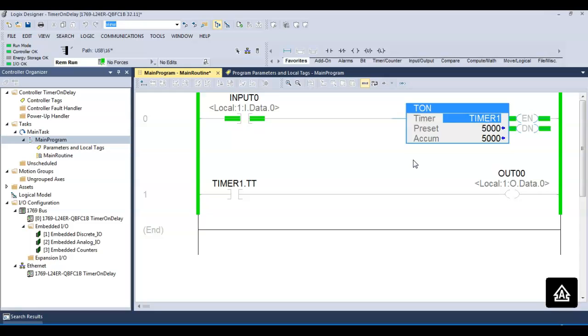So what's an array? It's a group of memory locations. And we'll show y'all in a minute how you can create your own array if you're going to keep some information you needed to get to real fast. So counters are going to automatically create an array. But it only creates it if you use it, right? So that's the big problem. One of the problems we have with RSLogix 500 is you've got all that memory out there assigned to timers if you don't even use what? If you don't even have a single timer in your program. So it didn't manage memory very, very well.